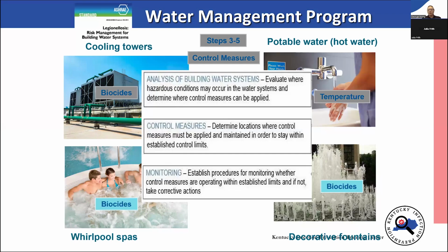Temperature is not the only way to control it in a potable water system. You can have a disinfection system. Some people will have secondary disinfection systems, such as monochloramine or copper-silver, added to the water on the cold water side before it goes to the hot water, to help eliminate or handle biofilm or colonization of Legionella throughout the system. So you can have a biocide in addition to temperature, but temperature is the most common control, as biocides are in the others.